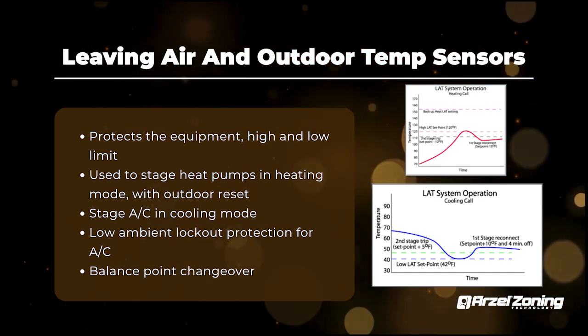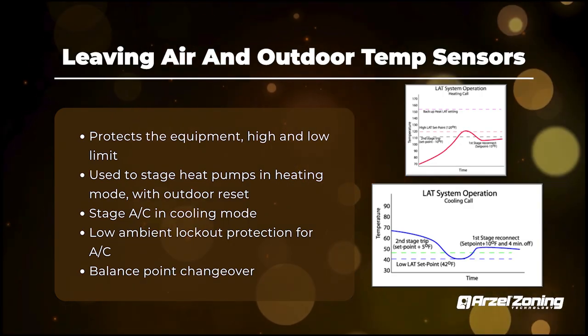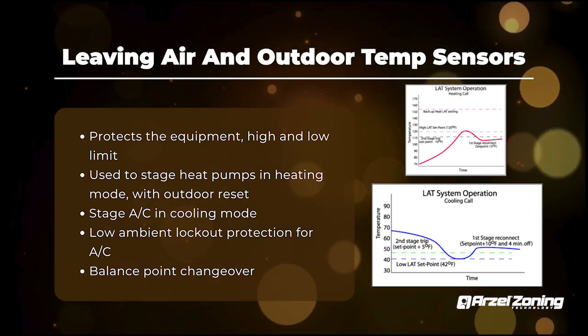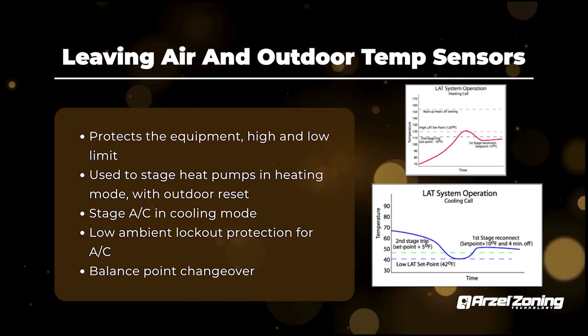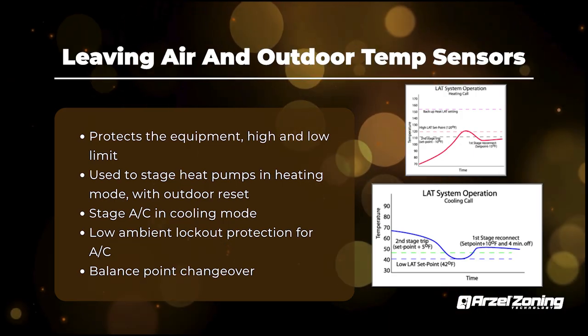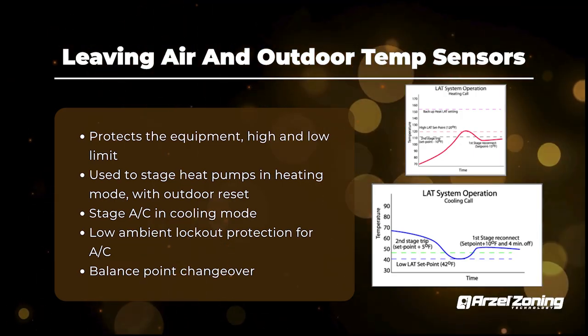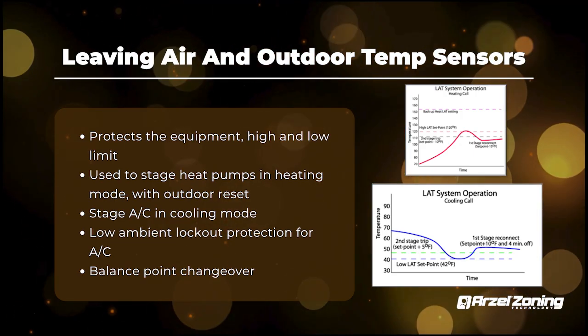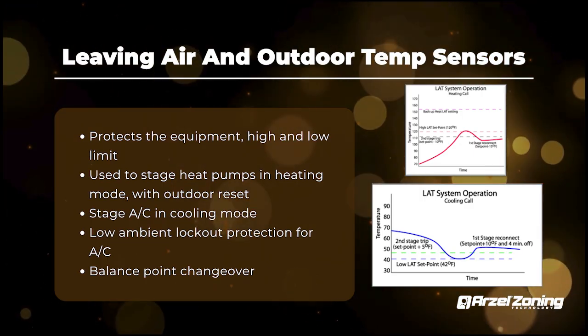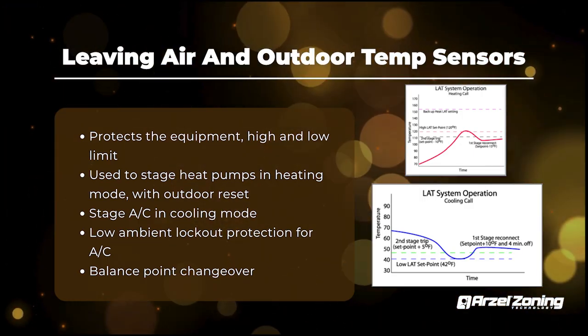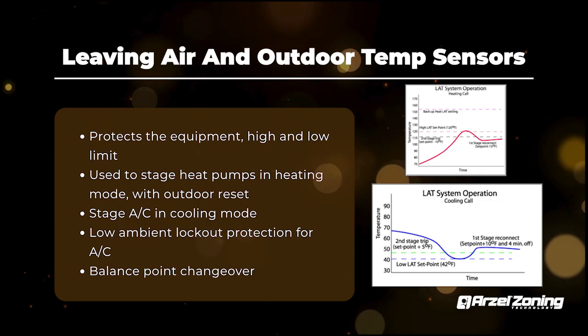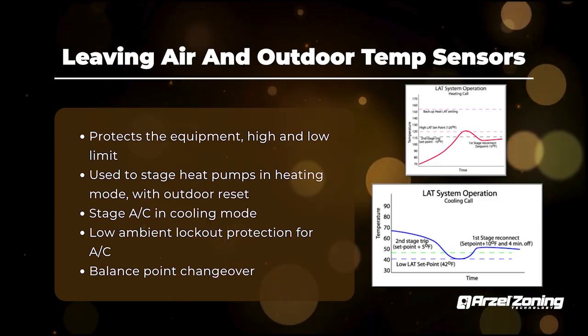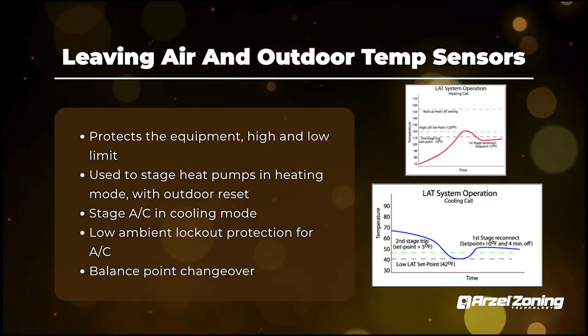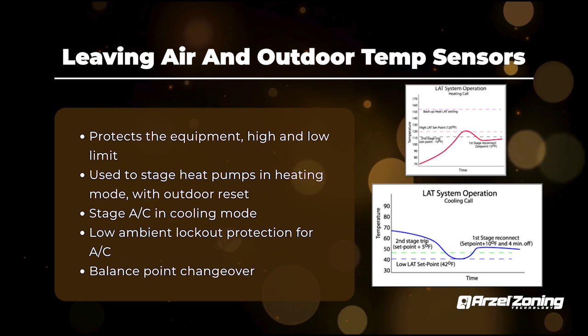And then there's a setting for heat stage and cool stage threshold in your settings. Cool stage is the temperature we're trying to maintain in the ductwork in cooling mode before we upstage the compressor. And your heat stage is essentially the same thing, but for heating mode. So we're trying to hit that temperature, and if we don't, we're going to upstage that equipment after 3 minutes and continue upstaging every 3 minutes until we satisfy that temperature. So that's how the staging works.